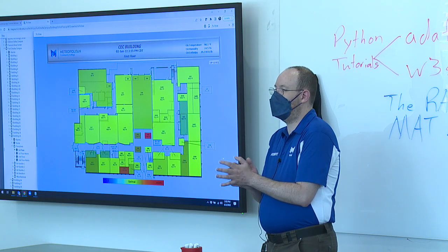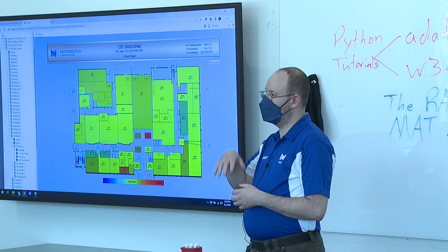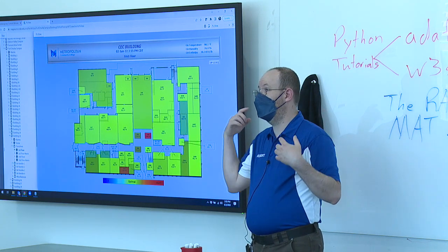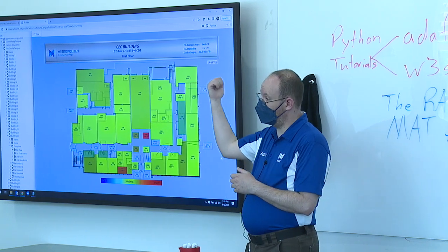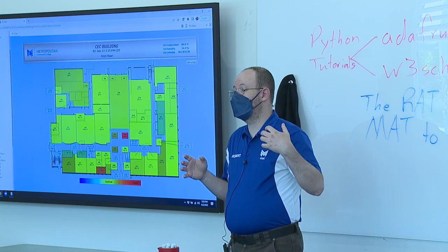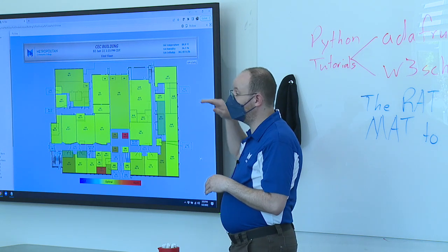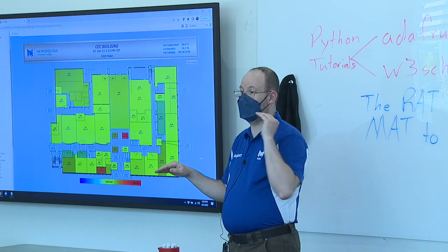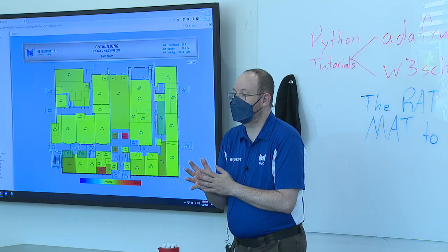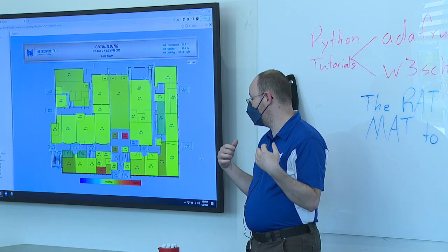It is possible that the reality of the design for this building was a little bit different than what got put on paper, because the engineering group that did all the mechanical design for all 3 of the new buildings and the central plant has worked with the college on a lot of projects. So they may have been slipped a piece of paper that says, really design for a 70-degree set point in the summer, and write down that you designed for a 74-degree set point. I don't think that's actually the case, because I have a big beef with how this building was designed.